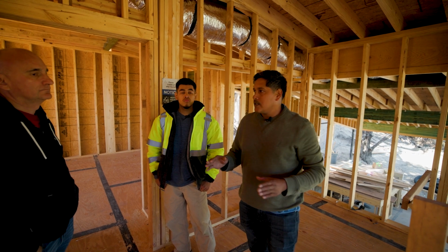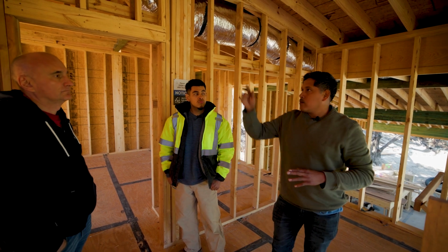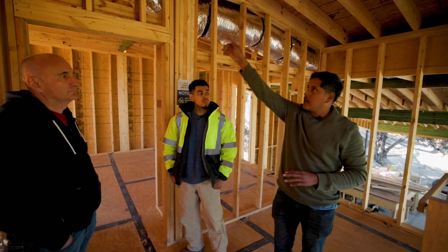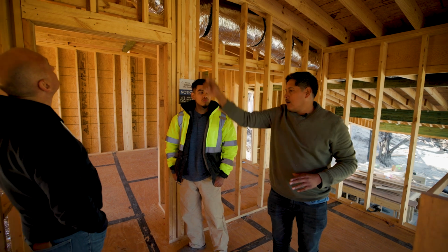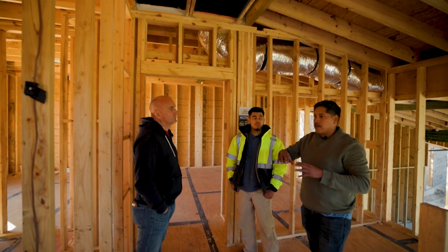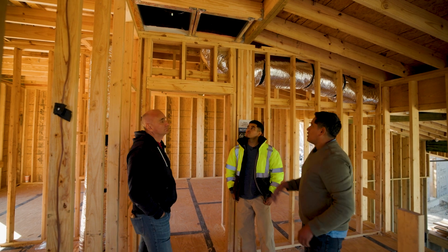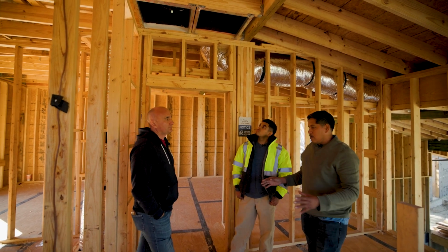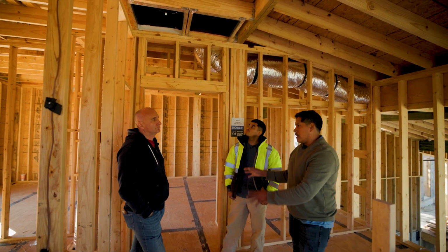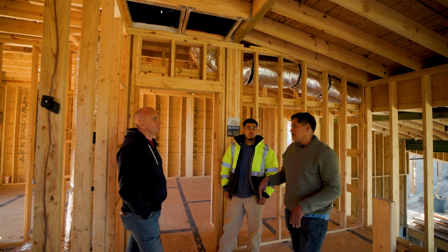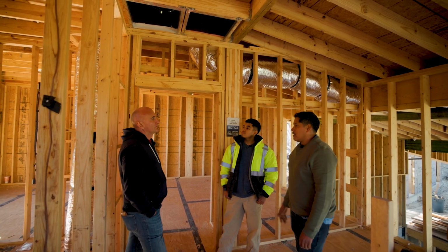We need to do our calculations so that if we have 3 tons, this return gives us the 3 tons. The CFM that we're going to pull out needs to come out of there. And the smaller your return, the more noise you're going to have in the unit. The client isn't going to like a lot of noise in the returns, because we have 2 units for this house, one for each unit.